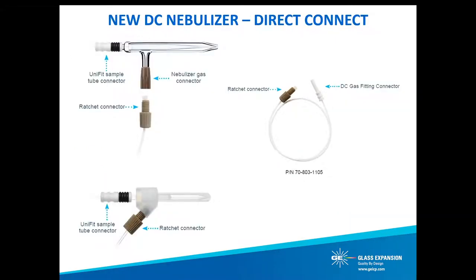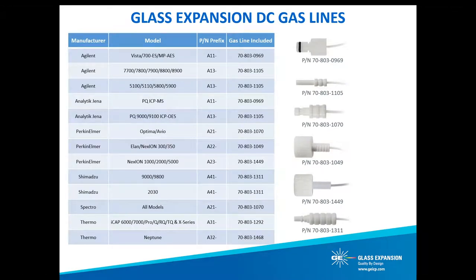In 2016, Glass Expansion introduced the Direct Connect DC gas line, providing an upgrade to our U-Series nebulizer product line with an inert metal-free ICP-specific gas line. The reliable ratchet click-and-seal fitting to the nebulizer gas arm ensures a leak-free gas connection by clicking or ratcheting when a proper seal has been achieved, preventing over-tightening. At the other end of our DC gas line is an ICP-specific quick connect to the argon gas supply. In the table, you can see a list of the variety of style gas connectors that are currently available and provided with each of our nebulizer models specific to that particular part number.